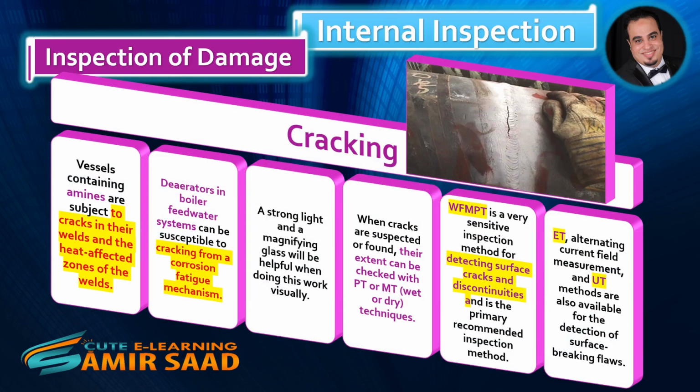Cracking. Vessels containing amines are subject to cracks in their welds and the heat-affected zones of the welds. Deaerators in boiler feedwater systems can be susceptible to cracking from a corrosion fatigue mechanism. A strong light and a magnifying glass will be helpful when doing this work visually. When cracks are suspected or found, their extent can be checked with PT or MT wet or dry techniques.